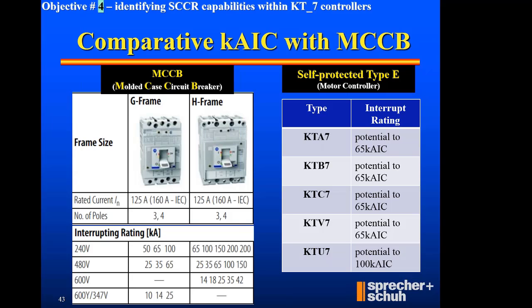On this screen, I give you a typical molded case circuit breaker as a comparison. When you're buying a traditional combo starter, you've got to spell out exactly what KAIC you're trying to achieve, because if you're not careful, they're going to comply with a circuit breaker down here at the bottom. You'll see under 480 volts that it could be a 25 KAIC kind of breaker. It could be a 35 KAIC kind of breaker. Or you could say, hey, Mr. Customer or Mr. Manufacturer, I need 65. So you've got to tell them up front what you want, and you understand what you may be getting with a molded case breaker. So it's all about being specific.